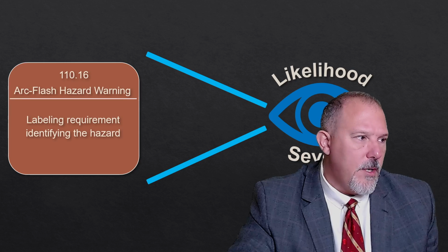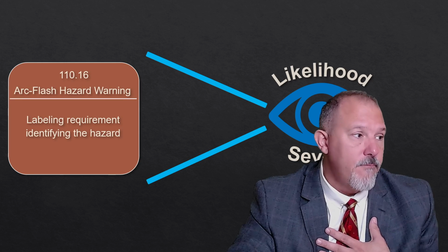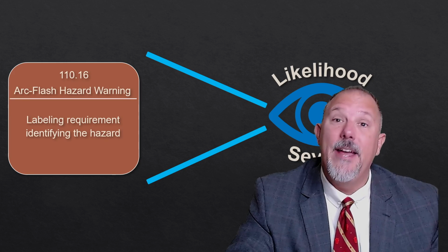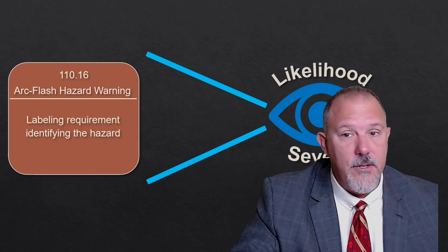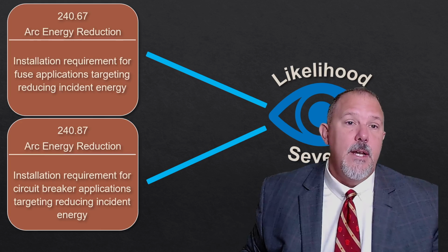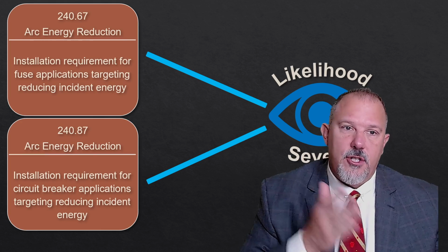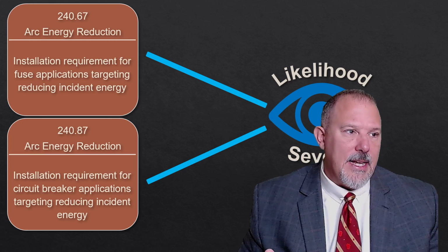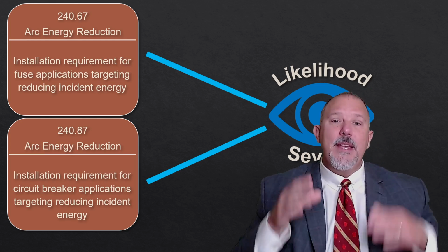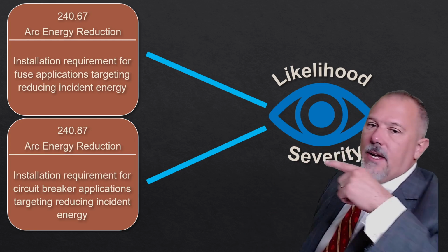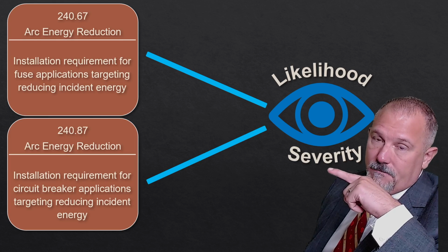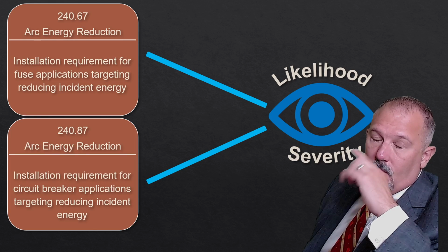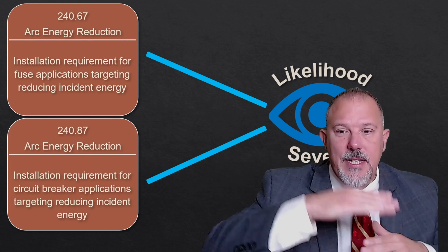Arc flash hazard warnings, in my opinion, help reduce likelihood. They don't address severity. 2 other sections, 240.67 and 240.87. 240.87, now, this is trying to address severity. Why? Because we're looking at reducing incident energy.